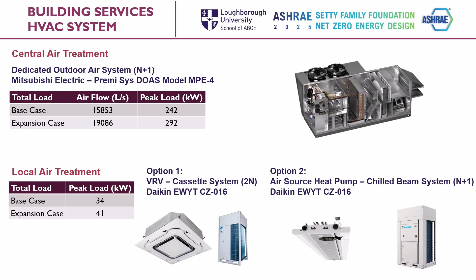The HVAC system will be designed using two peak cases, the first being the current building base case, and the second being the future expansion case, which includes the expansion of the third floor shell space, typical of the west wing of the first and second floors. The building will use a dedicated outdoor air system to supply pre-treated outdoor air, which will be further treated locally by either option 1, the VRV cassette system, or option 2, the air source heat pump chilled beam system. The HVAC components will be sized inclusive of a 10% safety margin and configured for part load and redundancies.